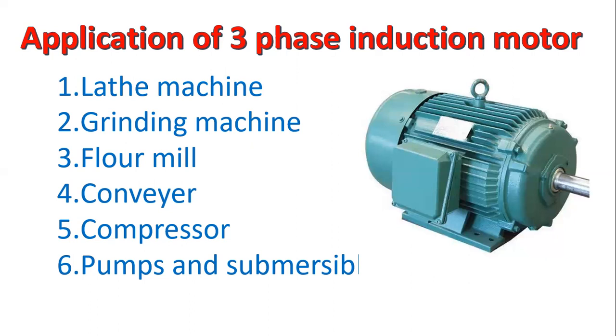Now the same as this, the compressor. In the compressor, the same type of load is used, preloaded. That means the compressor is also loaded before the motor starts. When the motor starts, this load is on the motor. But the motor has a tendency to carry 1.5 times the full load torque. So it can easily withstand this type of load.